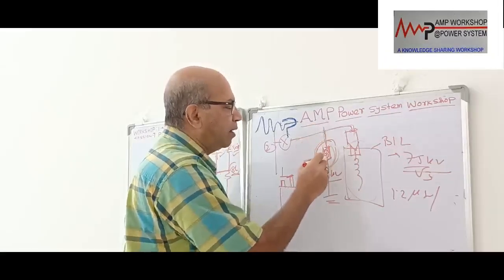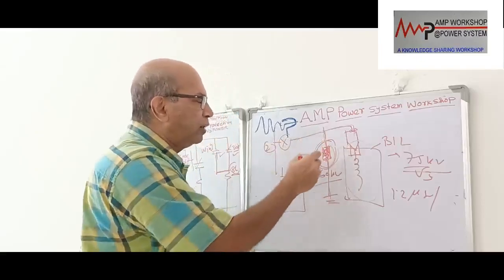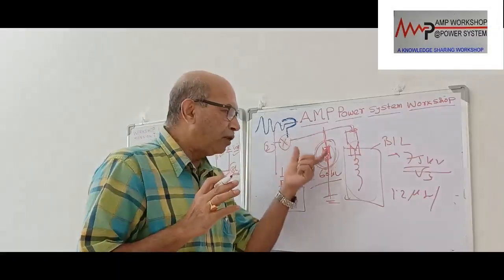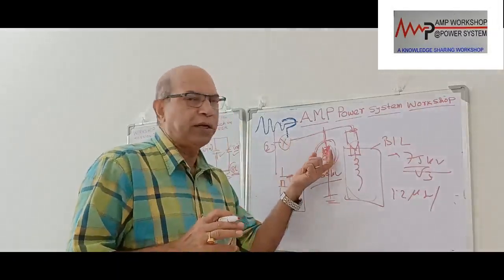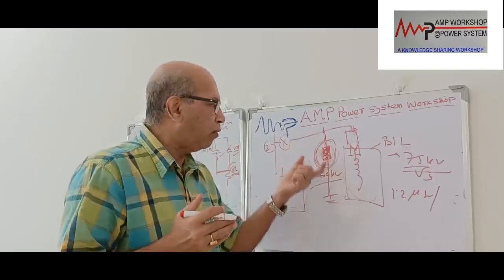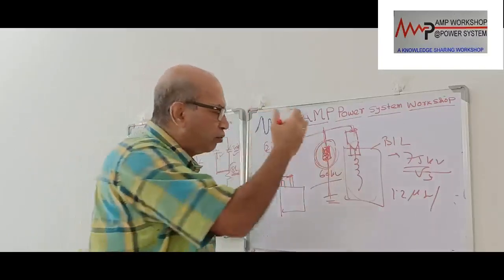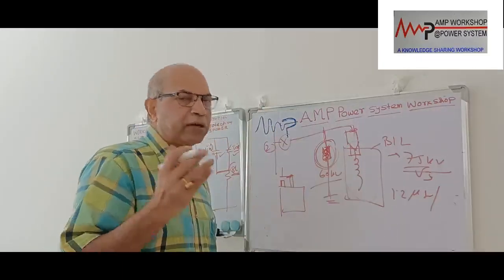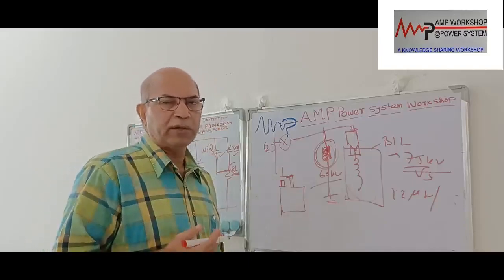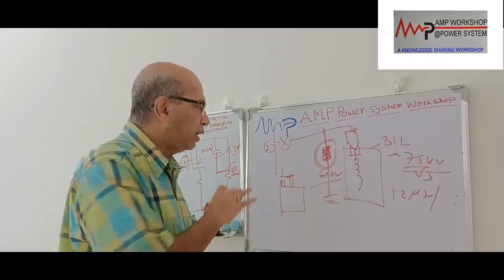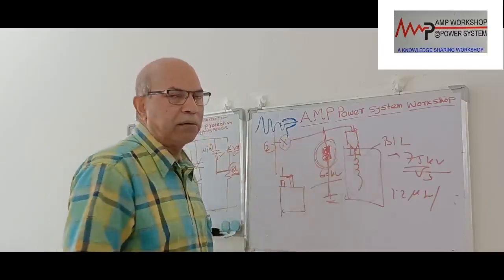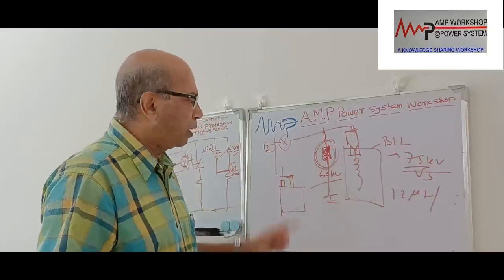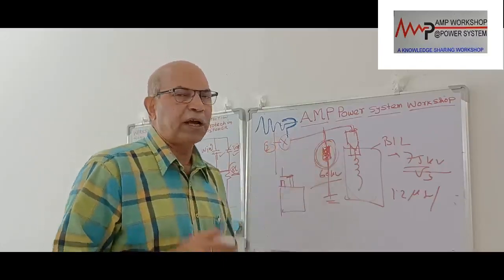When the high voltage comes, this metal oxide gets shorted and shows low resistance, because metal oxide is such a material that with the change of voltage its conductivity gets higher. So when this high voltage comes, immediately conductivity will be high, and it will conduct to the ground. That is the way the metal oxide works. The metal oxide arrestor we can use, we can use normal station type arrestors, we can use a horn gap also. Depending on the transformer cost, we can decide what type of lightning arrestor we need to provide to protect the transformer from the transient over voltage.